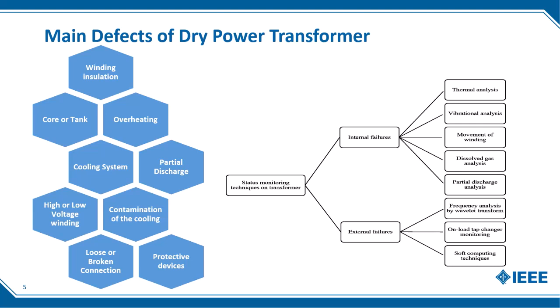Several monitoring techniques can be used to assess the health of a dry power transformer and detect potential defects. These include partial discharge measurements, a localized breakdown of the insulation in the power transformer. By measuring partial discharge, it is possible to detect defects in the transformer insulation.